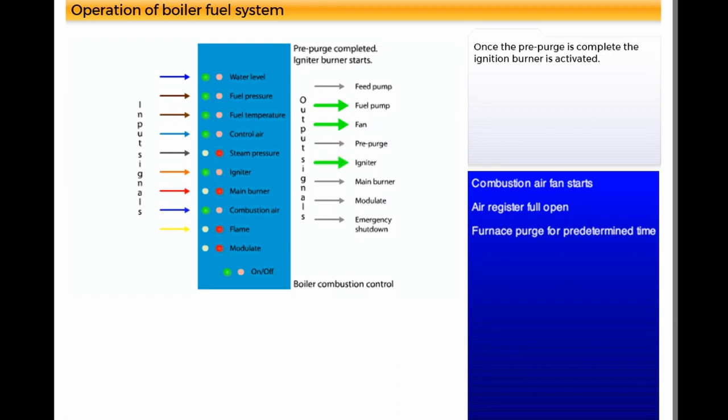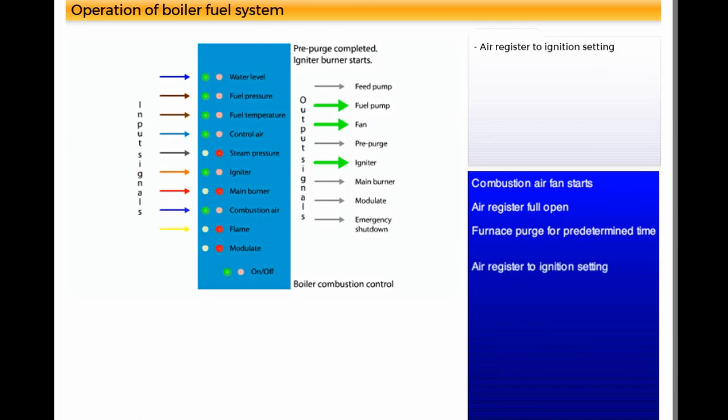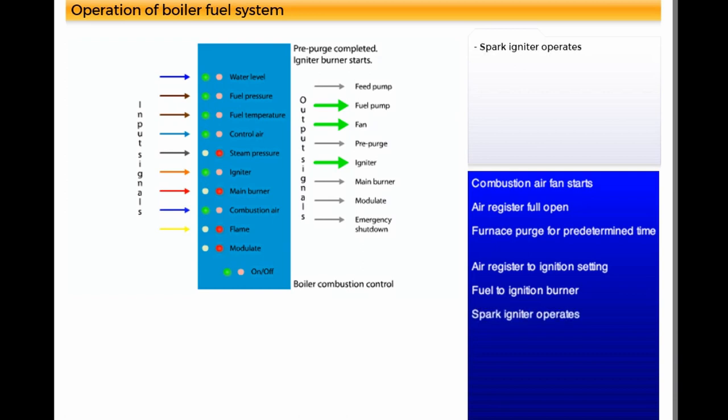Once the pre-purge is complete, the ignition burner is activated. Air register to ignition setting, fuel to ignition burner, spark igniter operates.